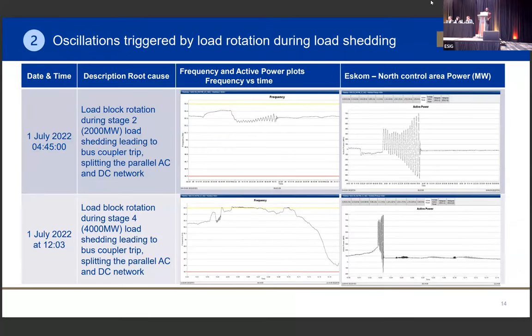The other type is oscillations triggered by load rotation during load shedding. If we are short of generation, we normally implement what we call load shedding. So 2,000 megawatts around the country, some customers will have close to 2 hours without power. We disconnect them after 2 hours, then we connect them, but we do it across the country. Stage six is about 12 hours without power, but not continuous. We switch off for 4 hours, and then switch it on, then the pattern repeats.